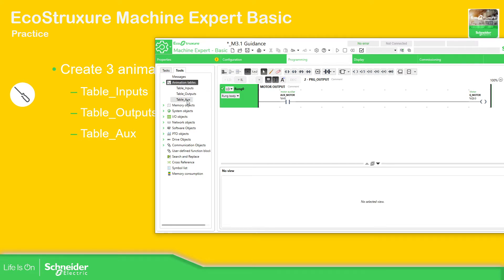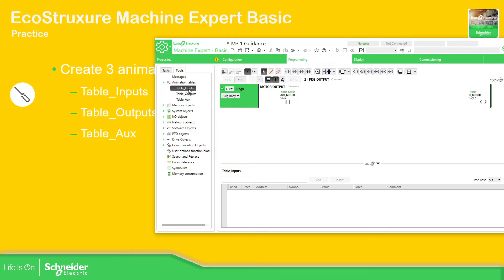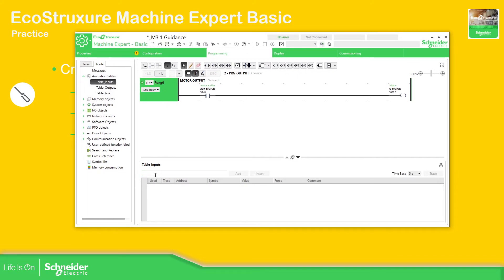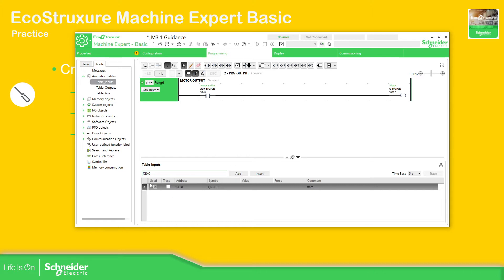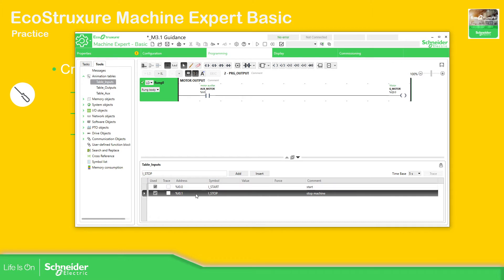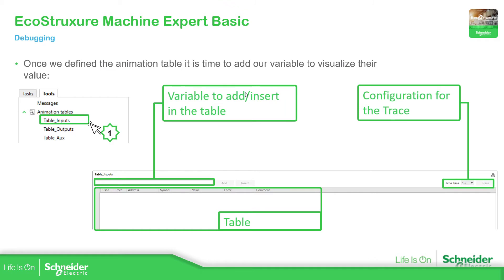Now we have defined all the tables that we want. Just one click on any of them and you can see in the overview that we have the possibility to add something here. For the input table, we start with %i0.0 — press Enter or Add or Insert to add the value. If we don't use the address we can use the symbol, so 'start' or 'stop'. We can add variables by symbol as well.